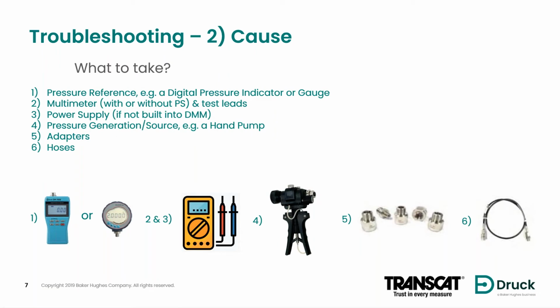And one thing that we can do is grab a number of items that we think we might need to test and check the site, the transmitter, the installation, etc. So we'll need a pressure reference, something that we know is working properly, to be able to check against the device or unit that seems to be having an issue.